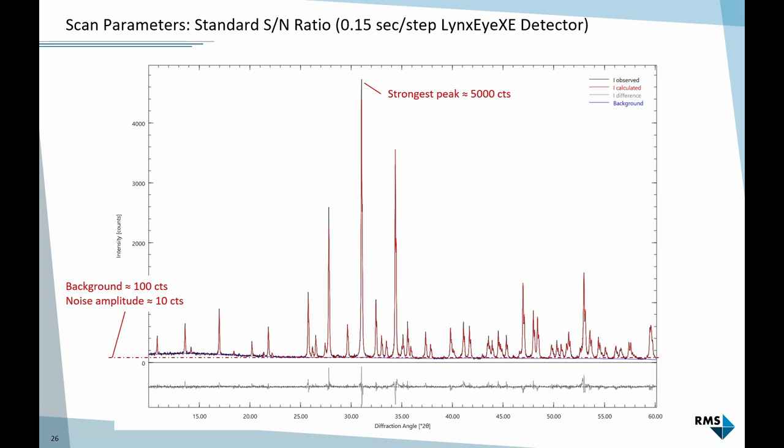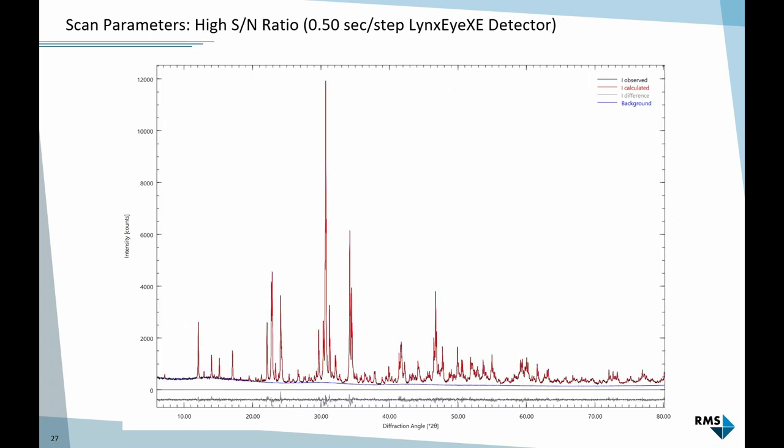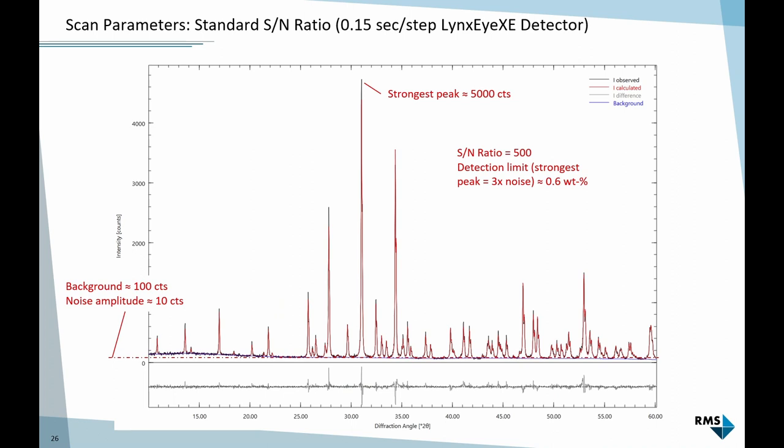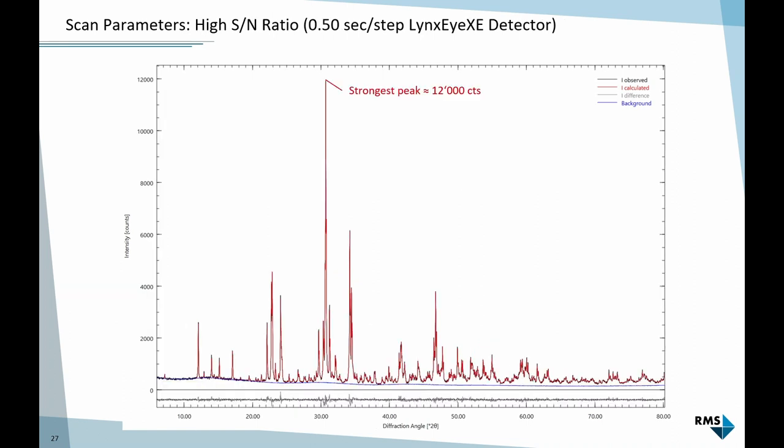Here's another example around 5,000 counts. It gives me reasonably low noise pattern - the strongest peak 5,000, background around 100 counts. That means the noise amplitude is the square root of 100, which is 10 counts. From this I can estimate a signal-to-noise ratio of 500, which translates to a detection limit of a bit less than 1% for this strongest phase. For ceramics with relatively complex diffraction patterns, that's quite okay. This was measured with 0.15 seconds per step. If I increase counting time to 0.5 seconds per step on the same instrument, I get about 12,000 counts on the strongest peak. My background is about twice the intensity, noise amplitude 15 counts. That would reduce my detection limit to about 0.4 weight percent, even though it's more than twice the counting time.